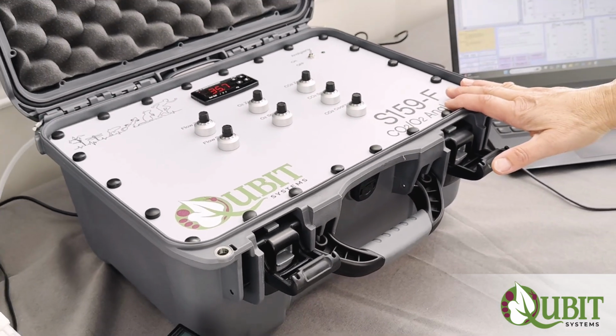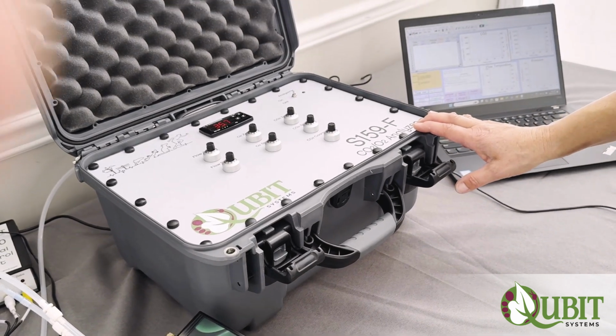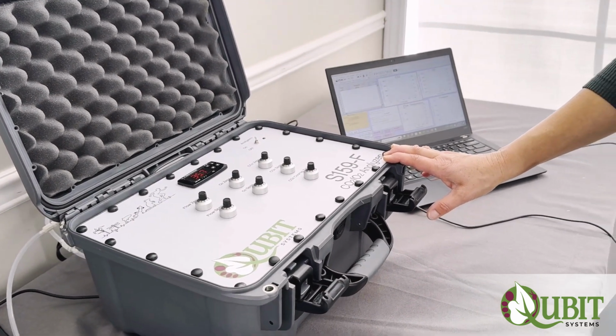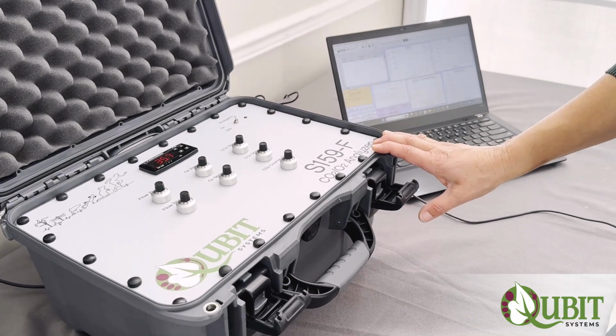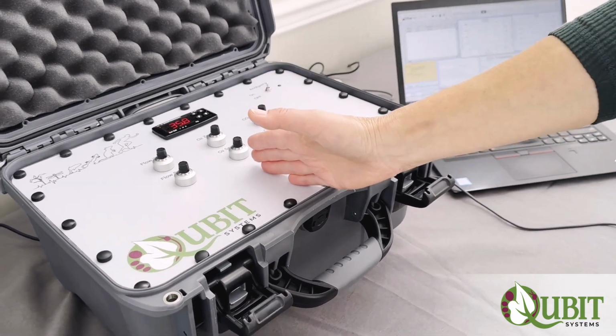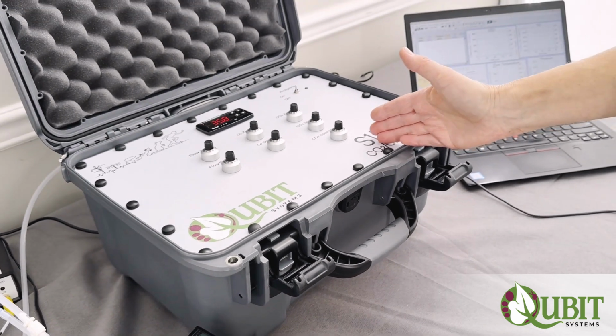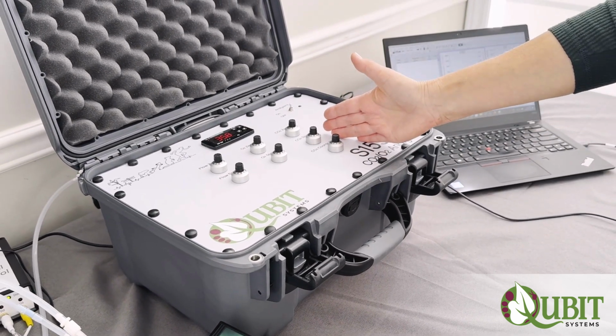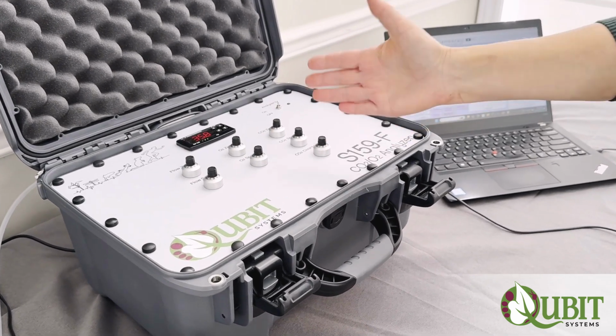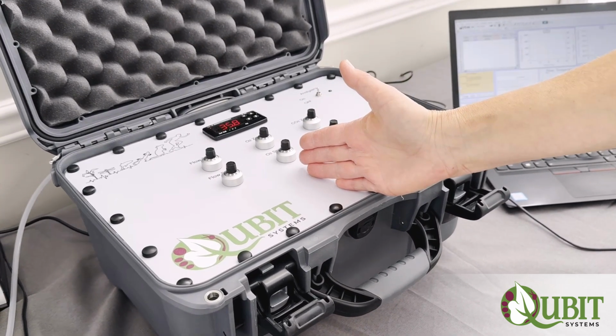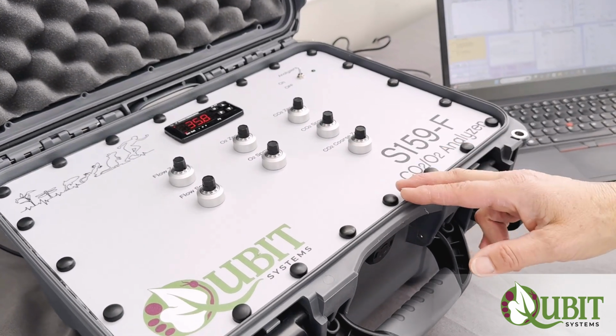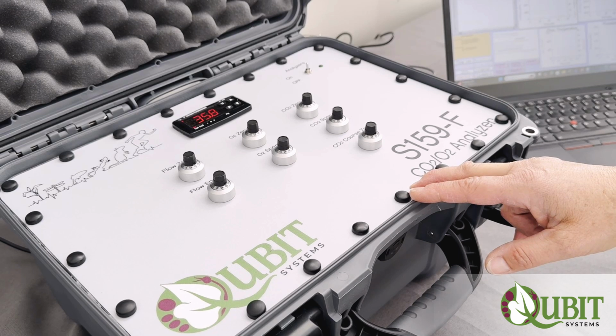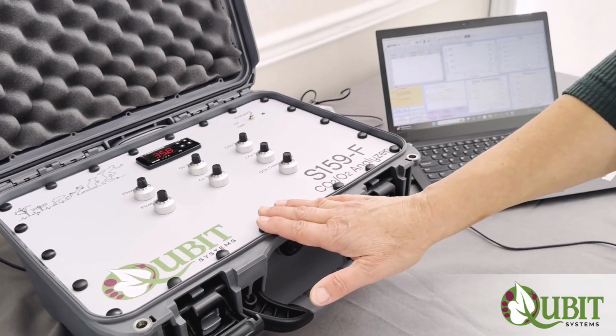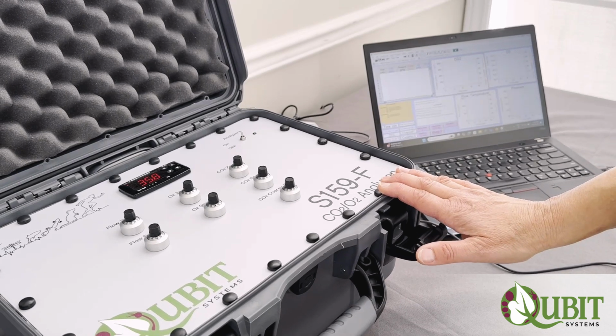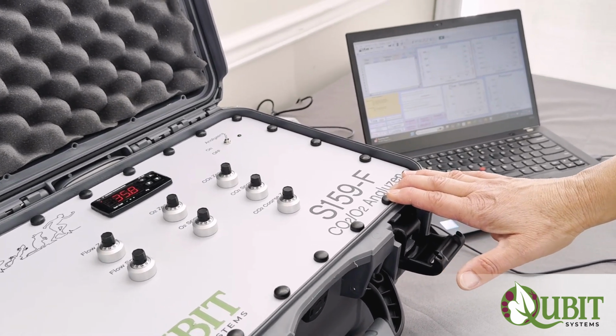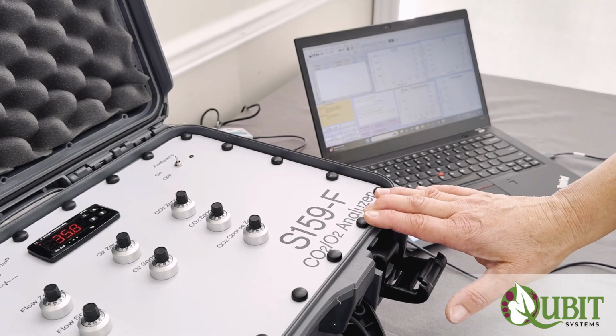So one only needs to have one gas tank for calibrating of the S159 analyzer. If you obtain a CO2 standard gas in the background of nitrogen, then you can use that same tank to calibrate the oxygen sensor and the CO2 sensor. And the second point for each: in terms of CO2, you have the soda lime, which is scrubbing CO2 to get 0. And for the oxygen sensor, you have outside air, which is providing 20.95% oxygen when it's dried through a soda lime column. So now both sensors are set up and calibrated, and basically the analyzer is ready to be used, and we will cover now how to set up the system with the gas switcher.